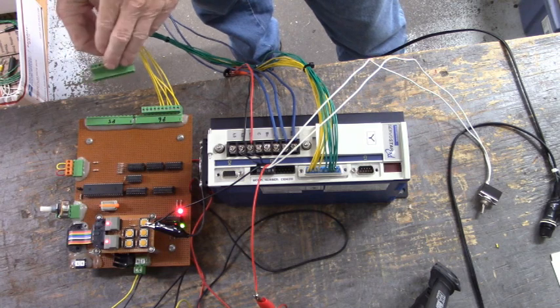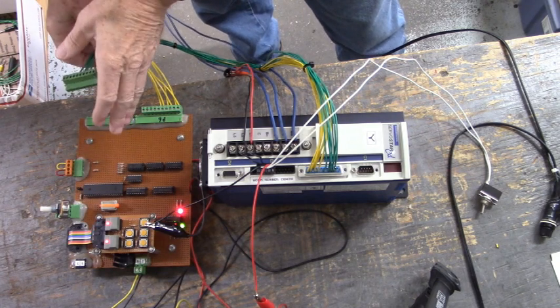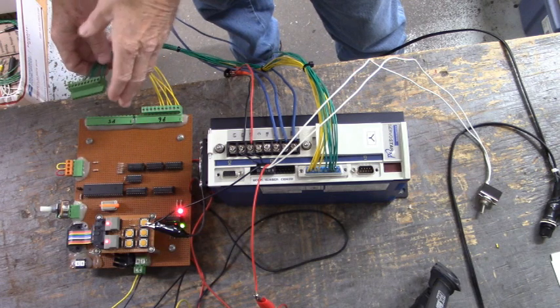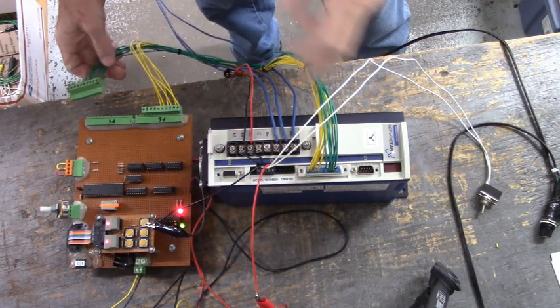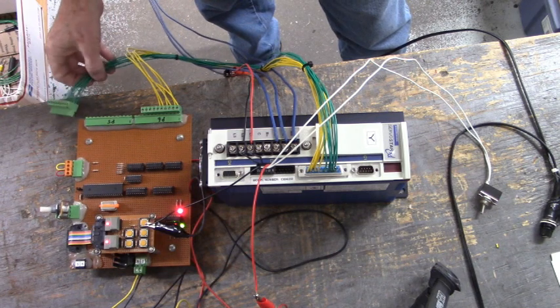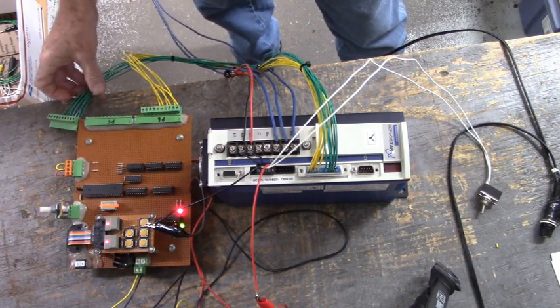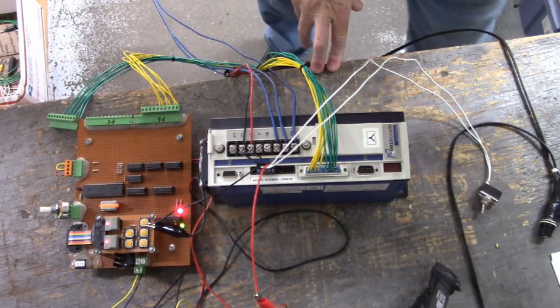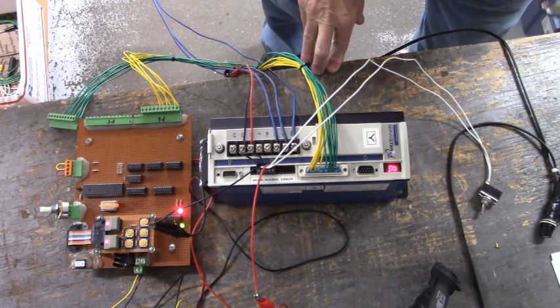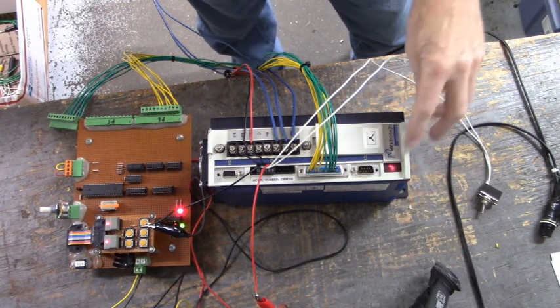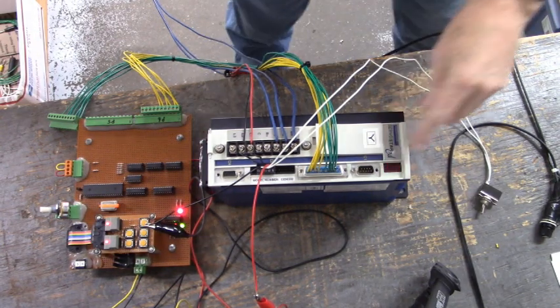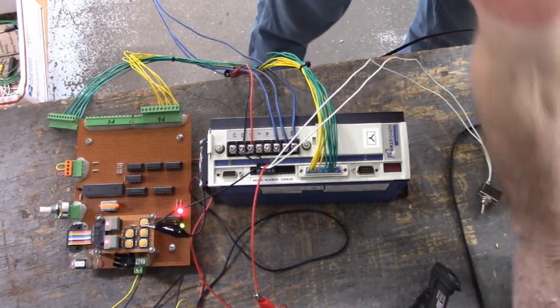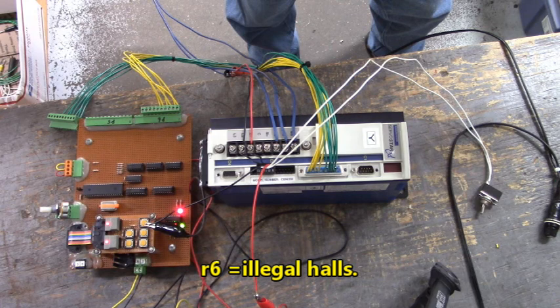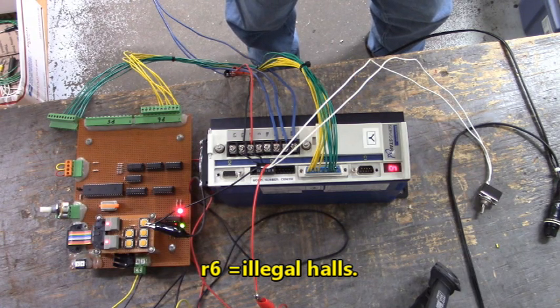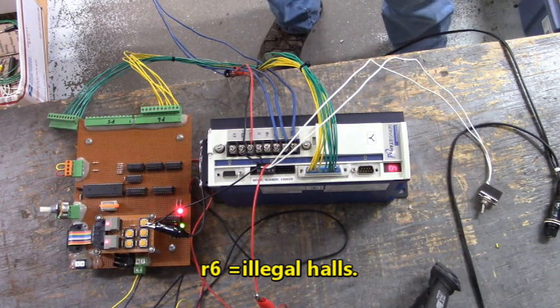Here I've disconnected the Hall effect side of my Hall effect encoder simulator, so that the only input is your incremental encoder input. With the Hall effects disconnected, let's see what alarm we get. Powering up the drive, we get R6 in the 7-segment display. Let's see what R6 says. R6, illegal Halls. Illegal Hall combination detected. I think being disconnected would be illegal Halls.